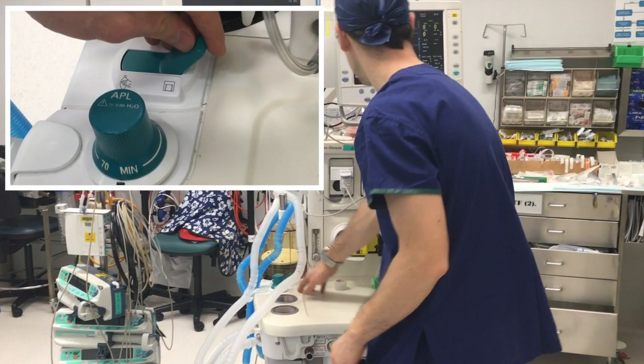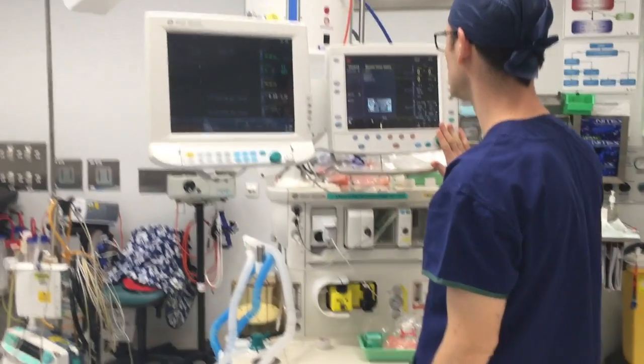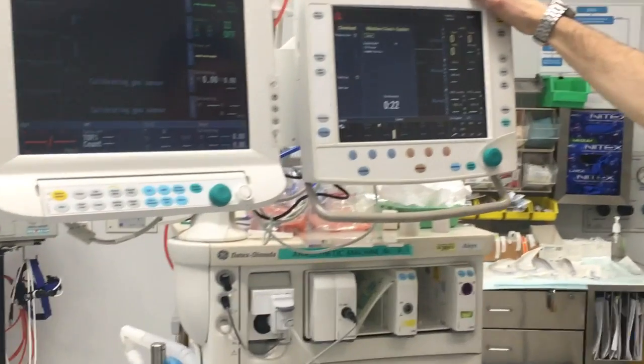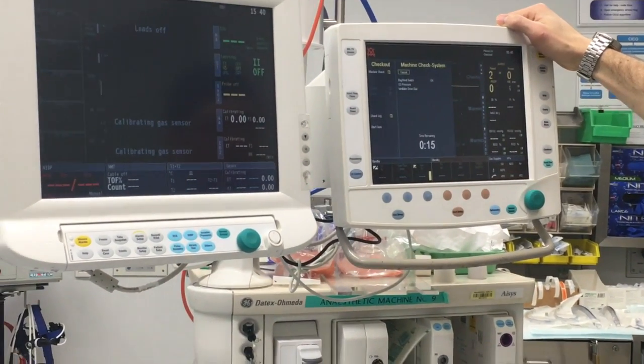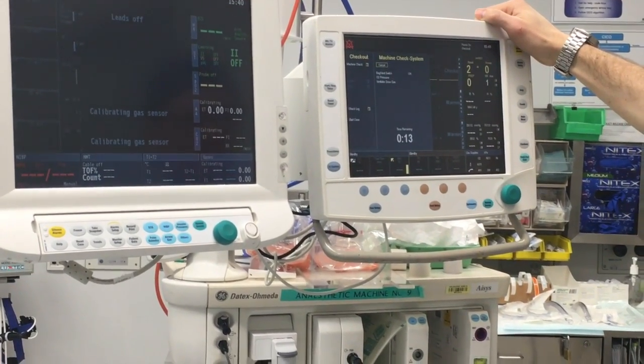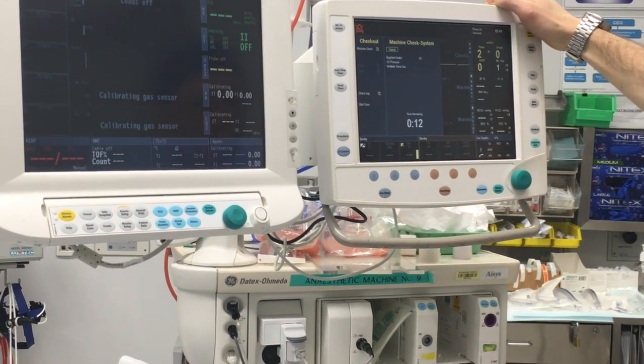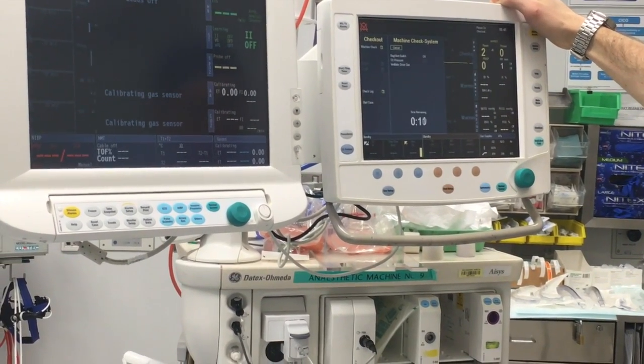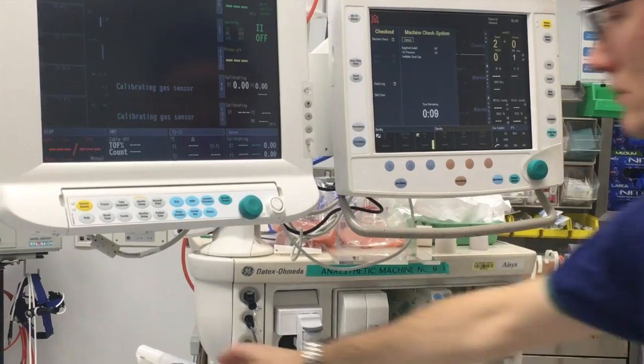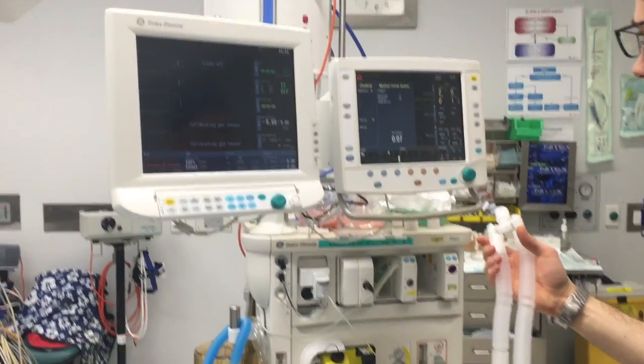Then make sure that this switch is turned towards the right. This allows the machine to do an automatic check of the ventilator circuit once you've pressed the green button. As the machine runs through its automatic checking processes, it can be a good time to anticipate the next steps and get the next pieces of equipment ready.